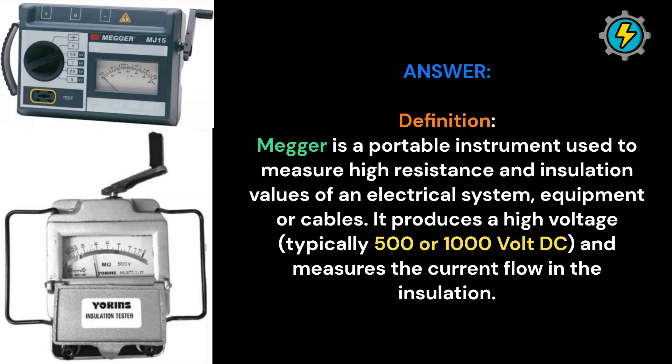Definition: Megger is a portable instrument used to measure high resistance and insulation values of an electrical system, equipment, or cables. It produces a high voltage, typically 500 or 1000 volt DC, and measures the current flow in the insulation.